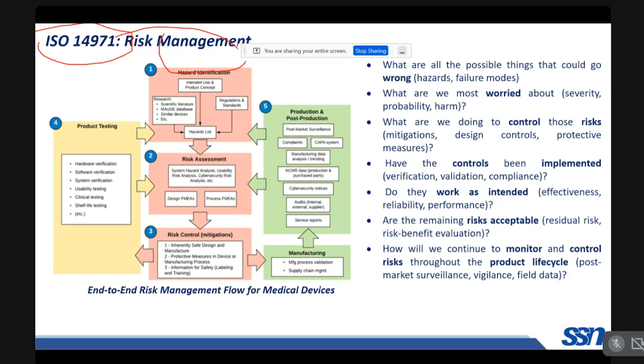Okay. In addition to that, this risk management process continues throughout the entire life of the medical device, and it does not stop once the device is sold. Once the medical device has been put into the market, the manufacturers collect data in the form of complaints, service reports, and new clinical information. Based on these, if new risks show up, they go back to their risk management file and evaluate how the risk occurs and what the control measures could be to remediate those risks. Okay. So this is all about risk management.